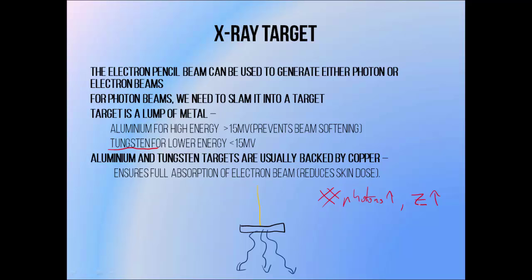Thinking back to photon interactions, in a high atomic number material when the beam energy is very high you also get a lot of pair production. This can decrease the energy of the beam being produced via beam softening, which is undesirable. So when producing very high energy photon beams such as 15 MV and above, we tend to use a low atomic number target material like aluminium. This helps to keep the beam energy high even if it is less efficient in terms of the number of photons produced. For lower energy beams we don't have to worry so much about beam softening because the pair production interaction is more rare, so we can use high atomic number materials like tungsten.